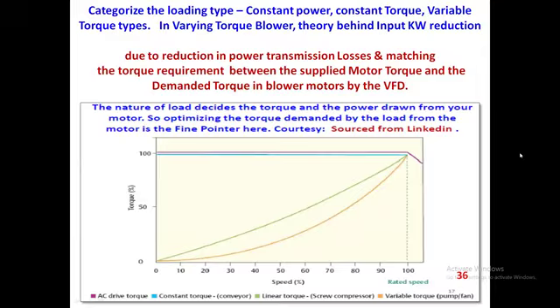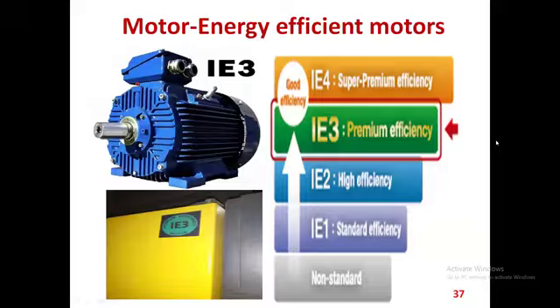The scope for energy saving is more in variable torque machines, because ultimately the motor power is directly related to the torque and speed. If you are able to manipulate the torque demanded by the load, and adjust it through the VFD, you can adjust the torque, you can adjust the speed, and definitely you can achieve savings. I'll come to that case study also.